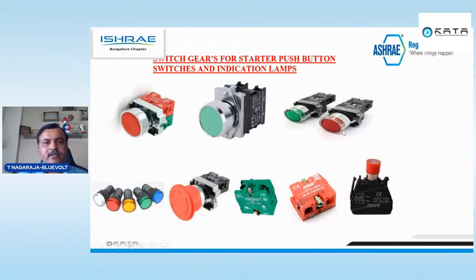That means whenever the motor is running, your red indication should be on. Whenever your motor is off, your green indication should be on. But without indication, for push buttons, it is reverse. When stopping, you have to press the red button. When starting, you have to press the green button. So the indication should be the opposite way. These are all the elements. The NO and NC elements will be used behind the push button stations.